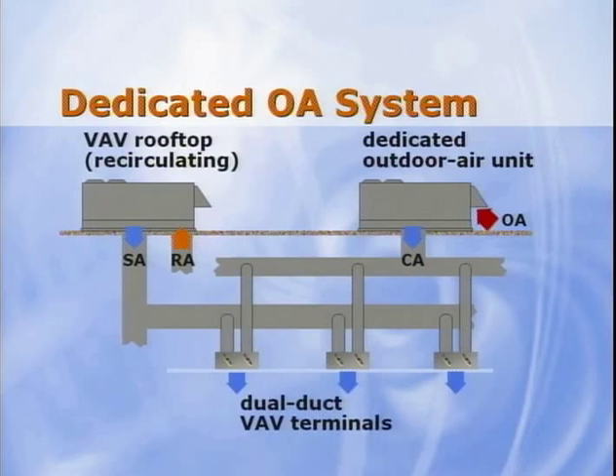Since the outdoor air is delivered directly to zone level VAV terminals, this is not considered a multiple space recirculating ventilation system. So the outdoor airflow delivered by the dedicated unit can be the sum of the zone ventilation requirements, which is typically less than what ASHRAE 62 would require of a conventional rooftop VAV system. In most applications, reducing outdoor airflow saves energy. Of course, the additional unit and duct system and the dual duct boxes do impact the installed costs.